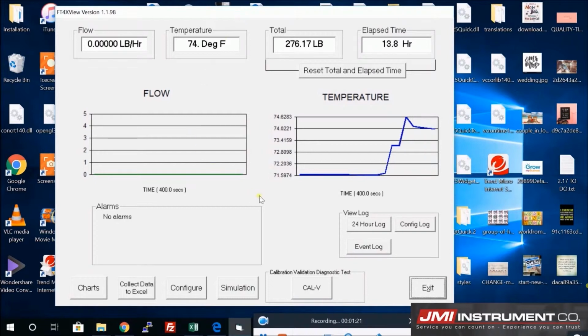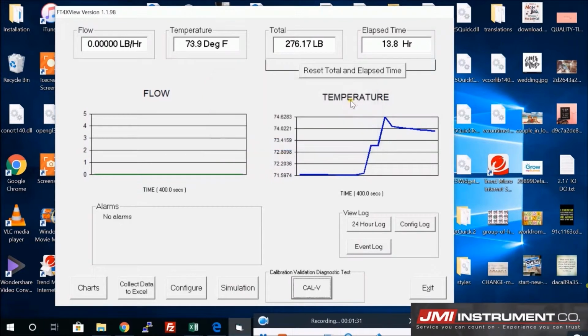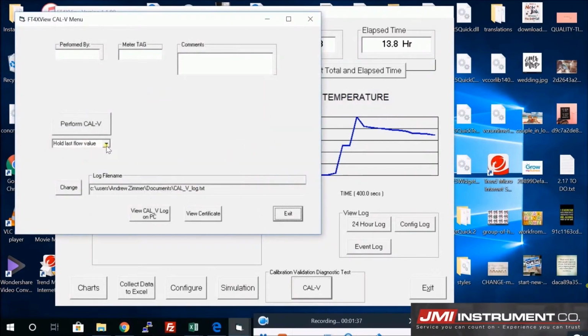If I want to run a calibration validation, I hit this button right here, Cal-V. And what this is going to do is allow me to keep the actual process conditions. I don't have to, although I can, run the process down to 0. I'm going to hold it exactly where it is.